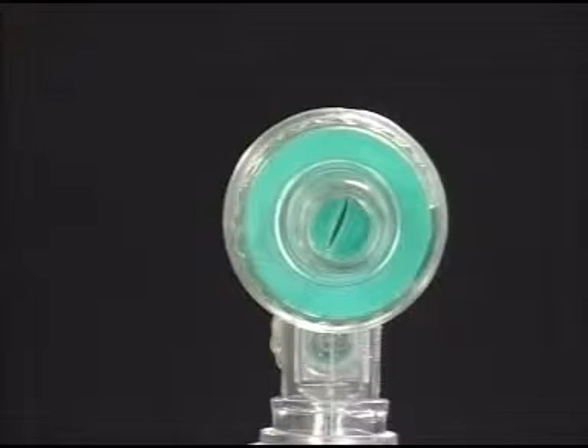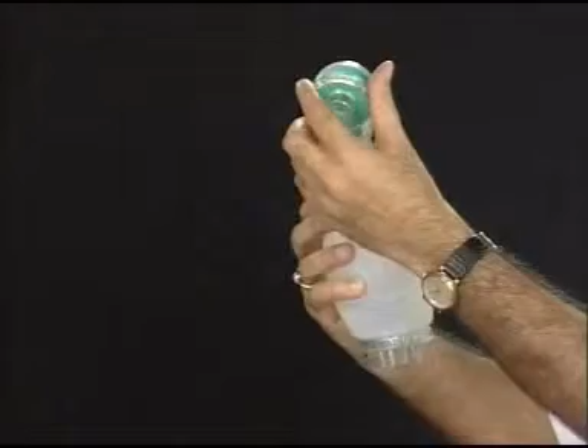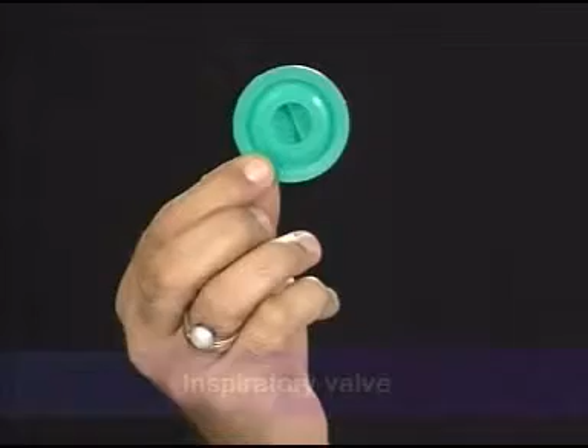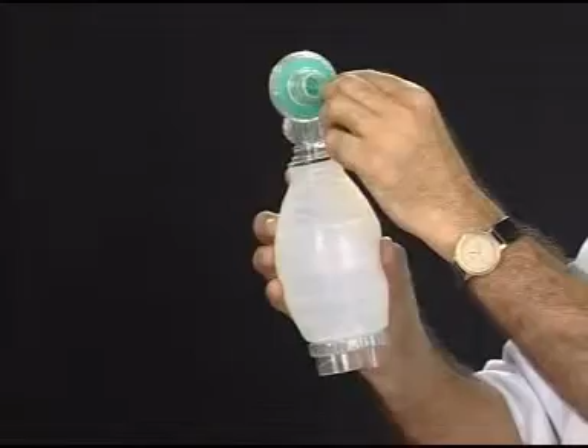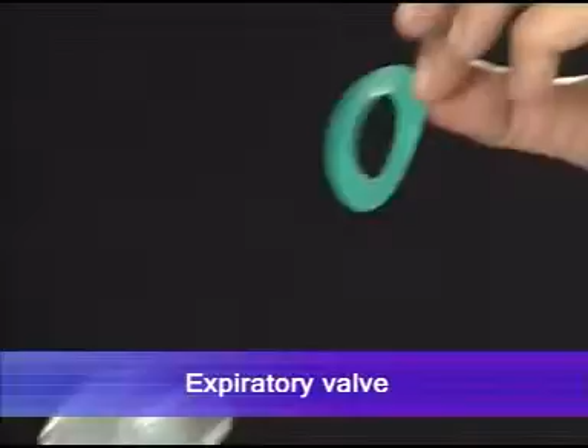Another valve is the inspiratory valve. Now this inspiratory valve one can appreciate by, when you squeeze the bag, you find there is a slit-like opening. When you squeeze the bag, you find that this valve opens like a fish mouth. One can see this also by opening this outlet, and this is the inspiratory valve. It allows only oxygen or the air to go to the baby. Another valve is the expiratory valve.